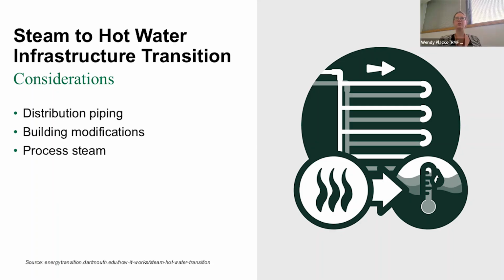So just to reiterate, you'd consider 140 low temperature hot water and 180 higher temperature hot water. And for the building to use that low temperature water, something would need to happen to make up that 40 degrees. Also, if they just put in brand new steam equipment, they're not just going to throw that out either. You always have to consider every aspect involved in a campus.